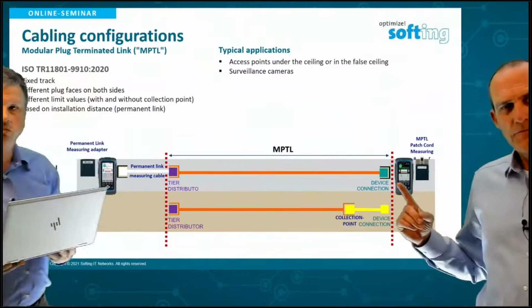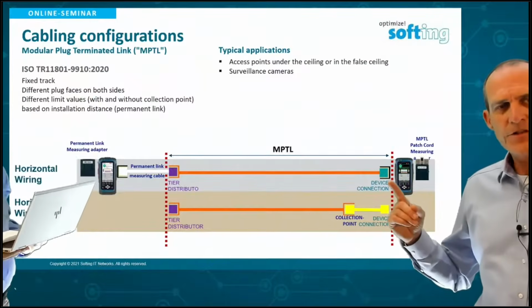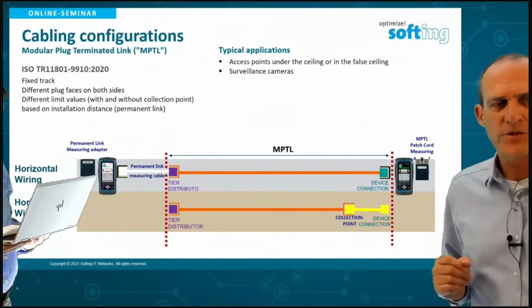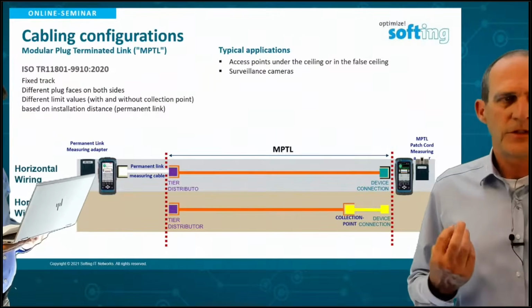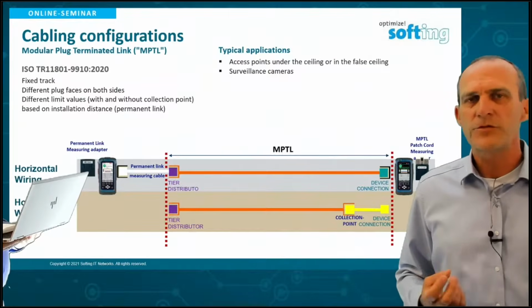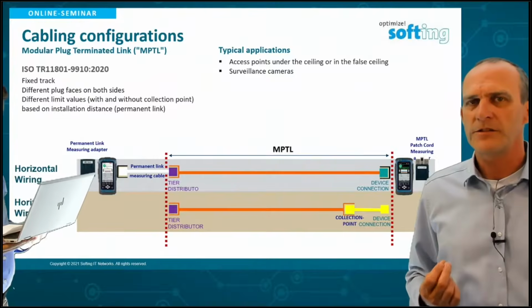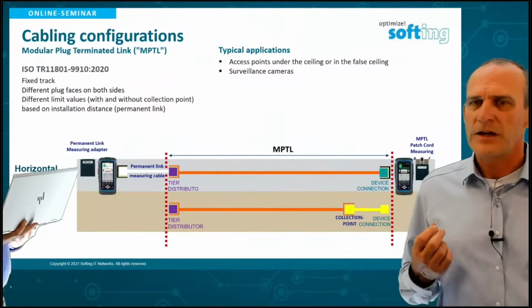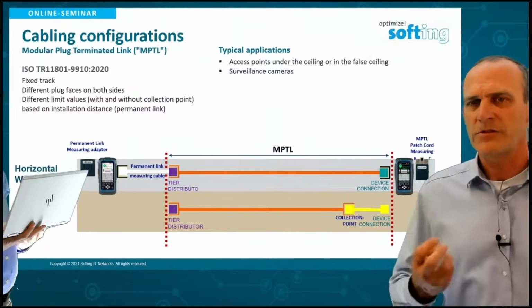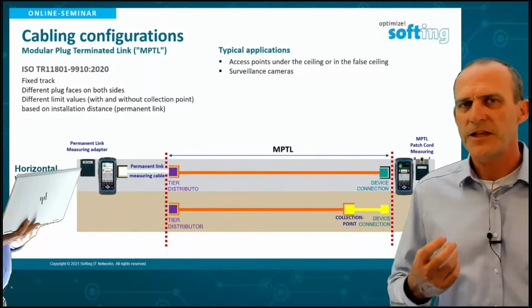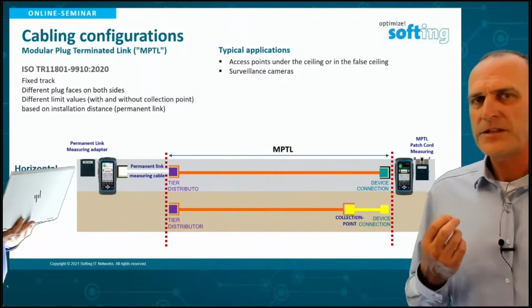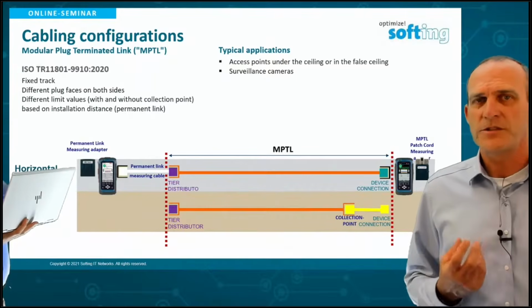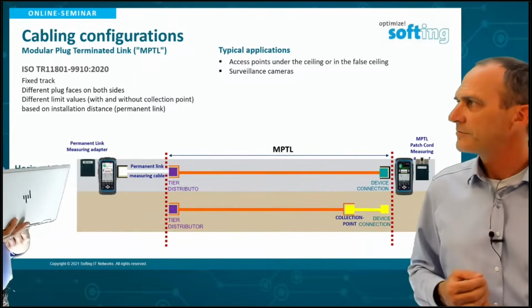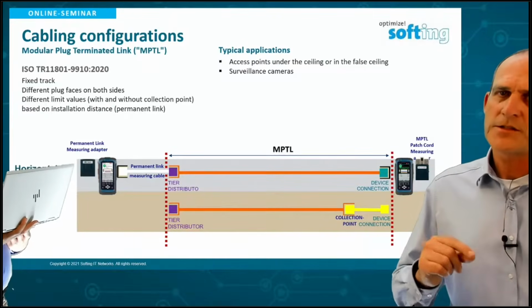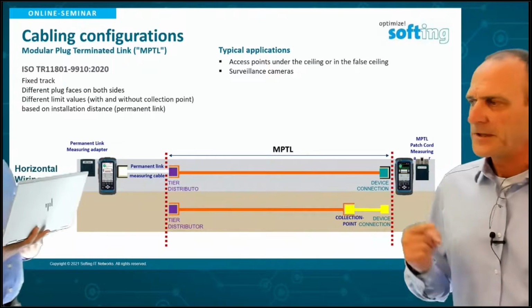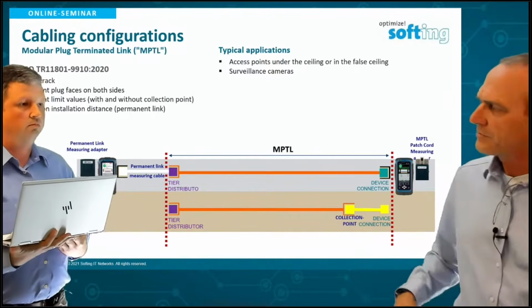You see that this first and last connector needs to be included in the measurement, and the standard says if you include that connector in the measurement, you have to test against a reference connector, and reference connectors are different for each category - category 5E, category 6, and category 6A. That's why we sell different MPTL and patch cord test adapters for each category of connector. If you don't do that, you're not testing according to standards, same as if you use channel adapters, for example.